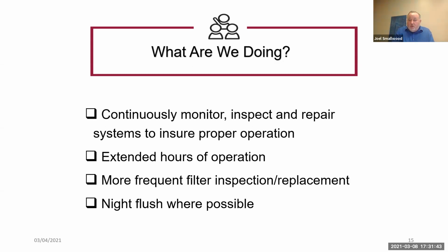But we certainly are working those systems to do that and to basically clear them out. That's the whole idea of the extended hours running from 6 a.m. to 6 p.m.: to have an additional morning clear out before everybody gets there, but it is heating the air at that point, bringing it up to temperature. And then at the end of the day, we let it run for, in many cases, several hours after people are gone, depending on release times, so we can clear that air out and start over fresh.